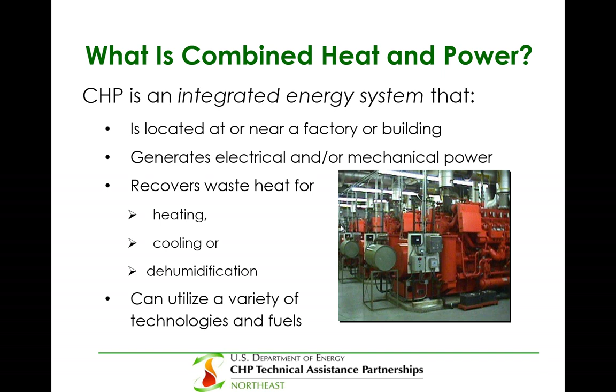So what is combined heat and power? I'm assuming some of the audience is not entirely well-versed in what it is. CHP is an integrated energy system located at or close by a building or a factory. It generates electrical and/or mechanical power, and most importantly, the benefit of CHP is it recovers the waste heat that's otherwise dissipated to the atmosphere, to cooling towers, or to bodies of water. That heat is recovered and utilized in a productive manner for heating, cooling, or dehumidification. CHP can utilize a variety of technologies and a variety of fuels.